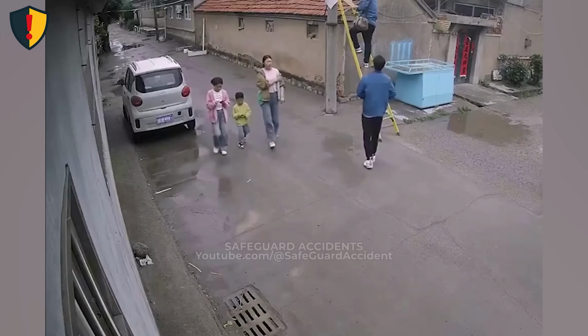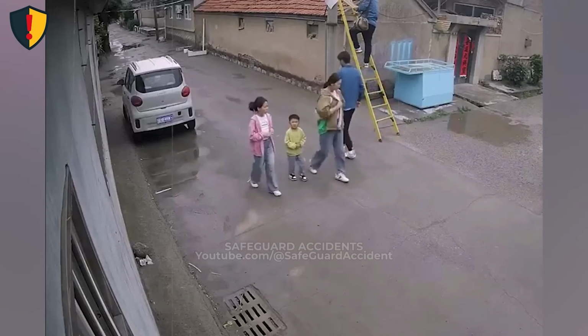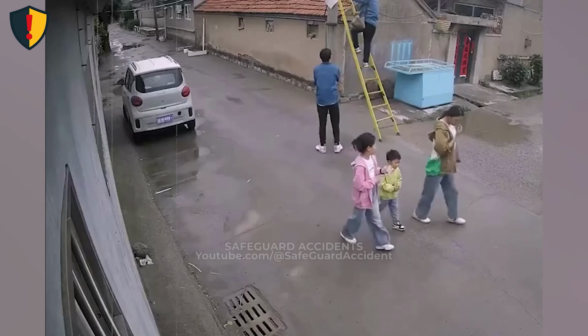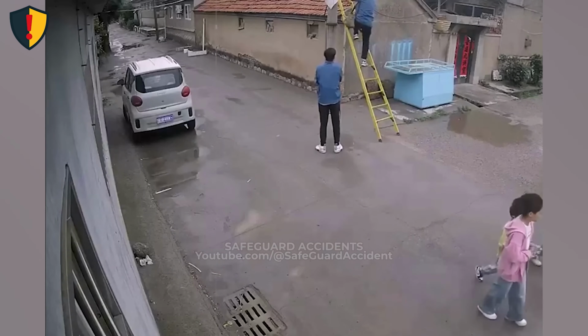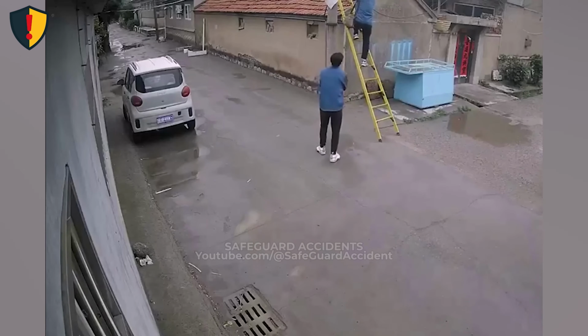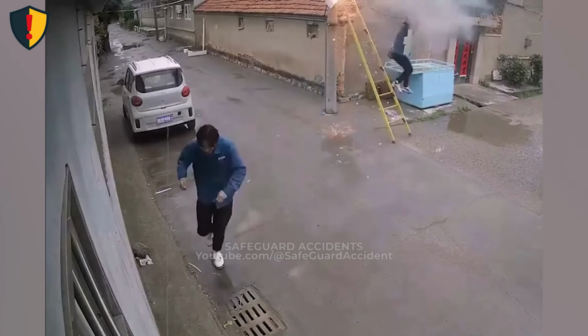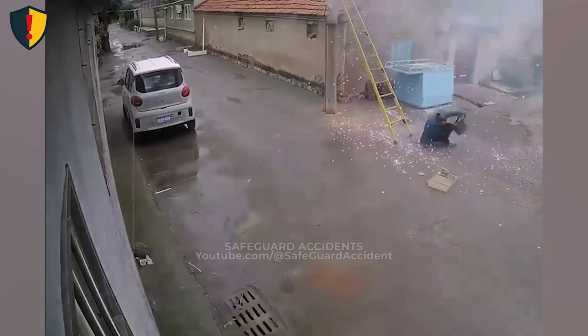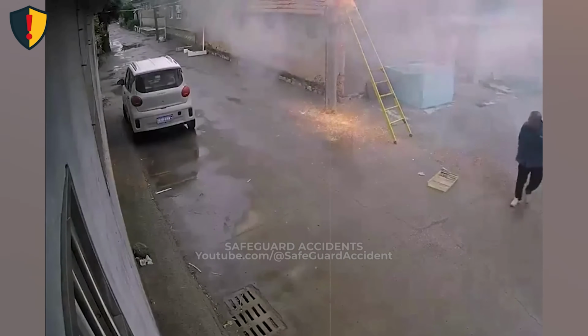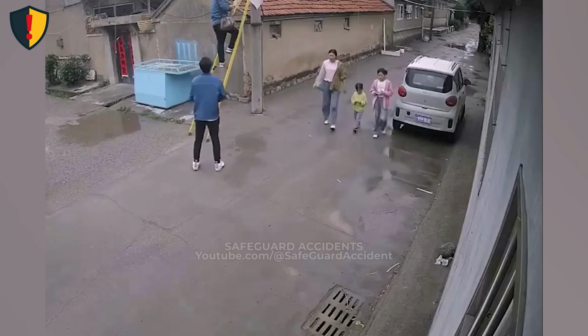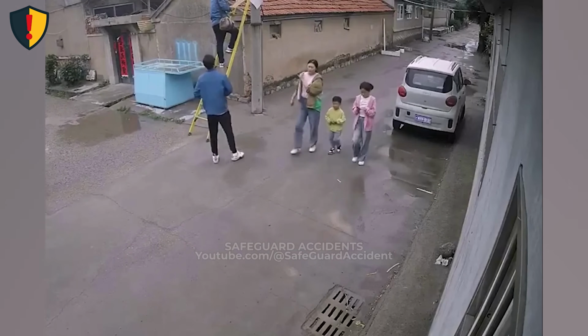On a rain-soaked street beside a concrete wall, a worker climbs a metal ladder, leaning against an electrical pole. Then a sudden arc flashes, and sparks explode outward in every direction. Do fully isolate electrical sources, verify de-energization, and use insulated ladders and protective equipment when working near power lines, especially in wet conditions where conductivity is significantly increased.